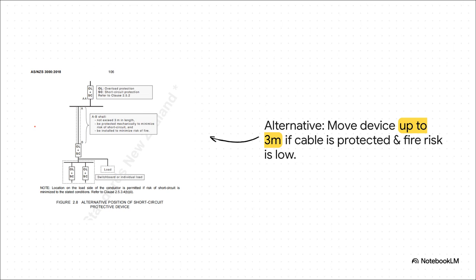But hey, the standards are written for the real world. And sometimes putting a breaker right at the origin just isn't practical. So there's an exception. This clause lets you move the device up to 3 meters down the line. But, and this is a big but, that little section of unprotected cable has to be rock solid, mechanically protected, and installed so the risk of a short circuit or fire is basically zero.